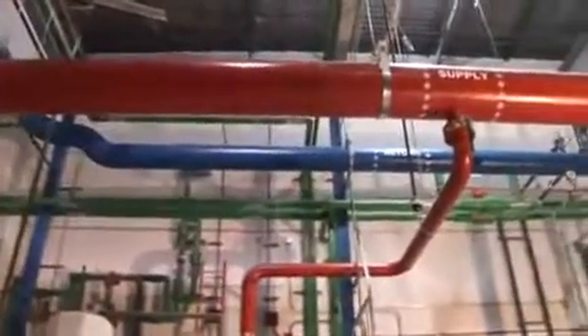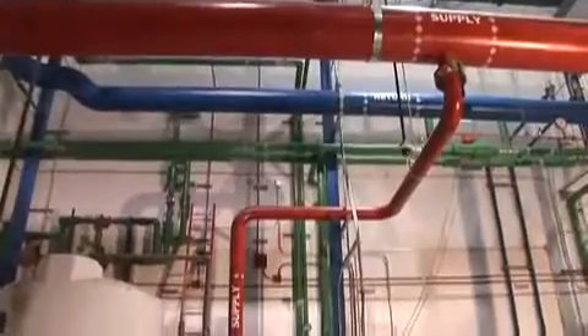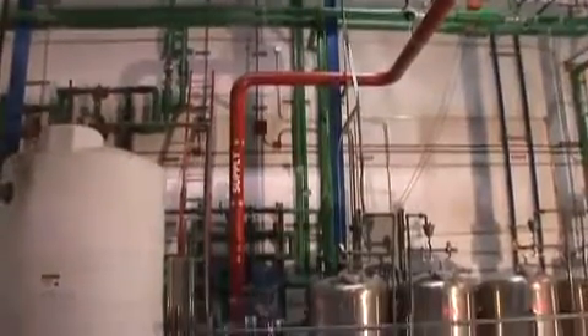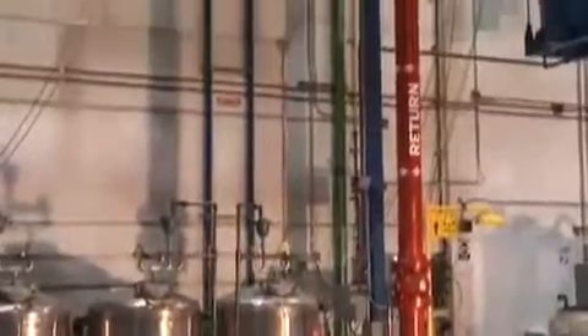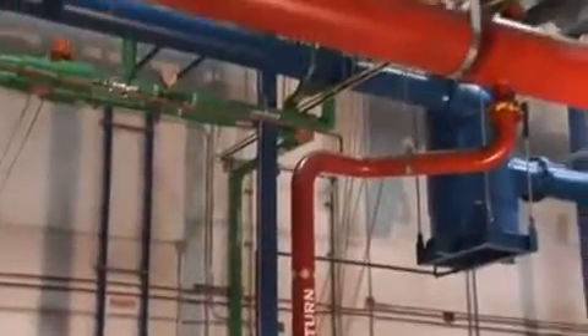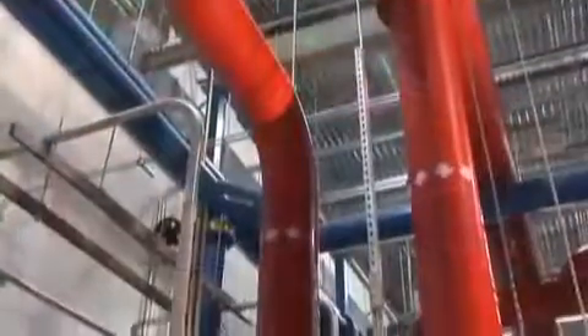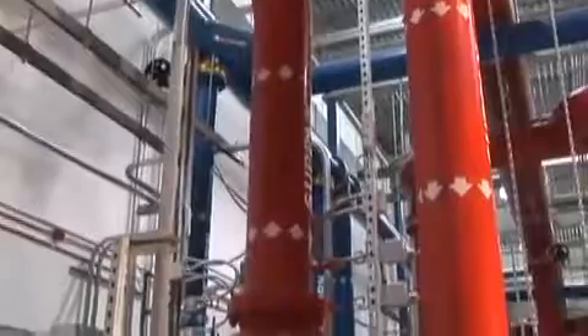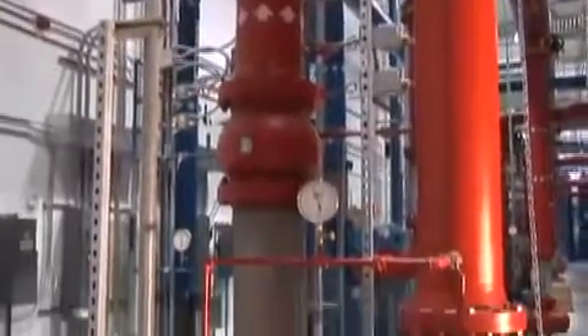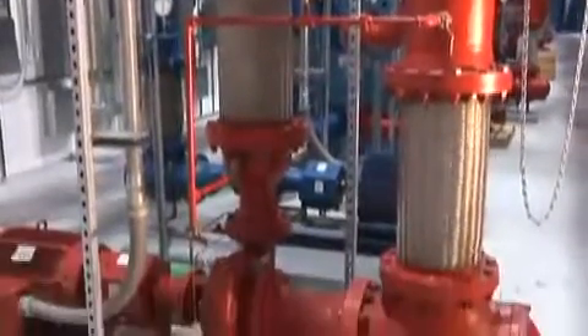As the water returns from the cooling towers, a portion of it is taken off and directed through a side stream filtration system before being returned to the loop. Continuing on, we trace the piping down to the array of pumps where we see that we experience our share of leaks.